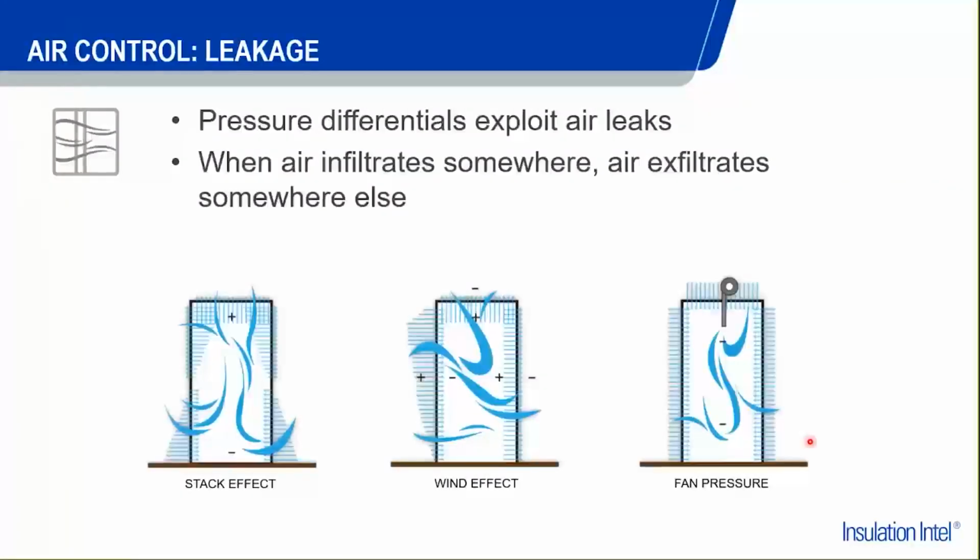So buildings themselves function to pull in air and expel air through the building structure itself. The stack effect, even though controlled between floors in a commercial structure, can actually move up through a building core if air is allowed into that core, if it's not pressurized correctly. MEP engineers work to compartmentalize the different environments within these buildings, and sealing the air movement between those environments will address a lot of the pressure differentials which are created by the stack effect.